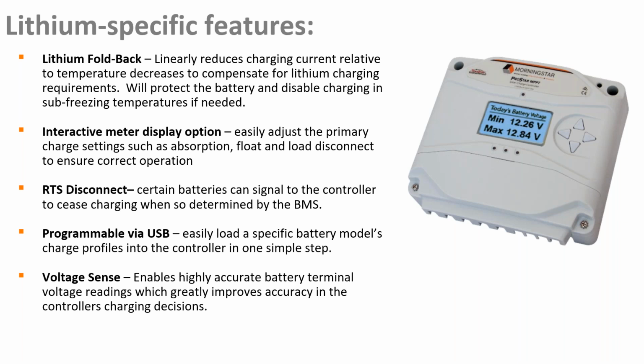temperature threshold. What that instructs the controller to do is perform a linear derate of the charging current from reaching the high threshold all the way down until it reaches that low threshold cutoff, so that you ensure you're still allowing what can be accepted by the battery all the way up until that hard cutoff when you need to stop all charging. So again, that's a popular feature used for lithium battery charging.